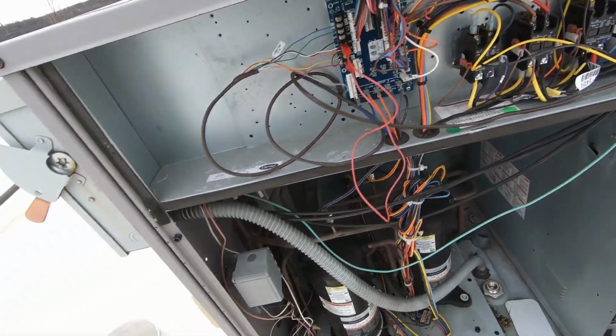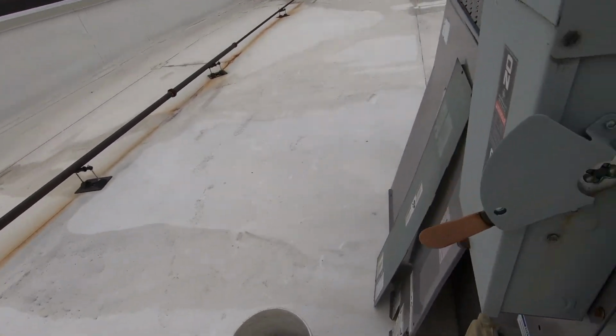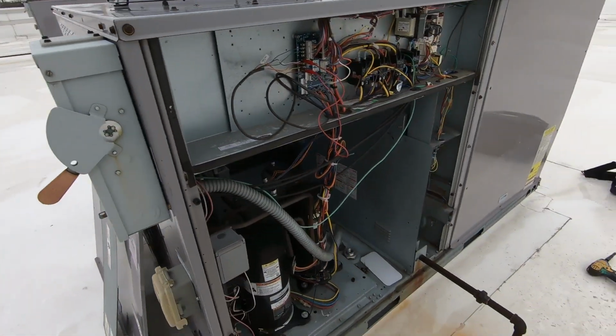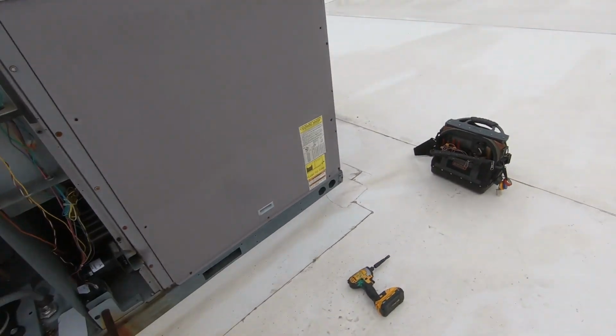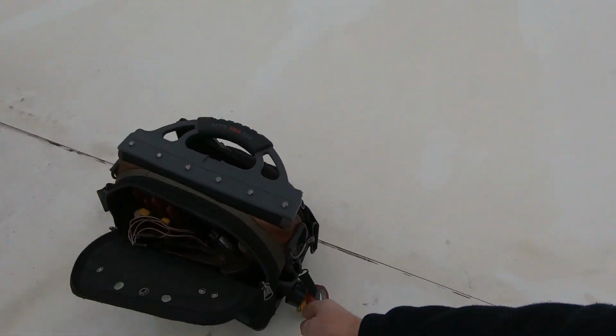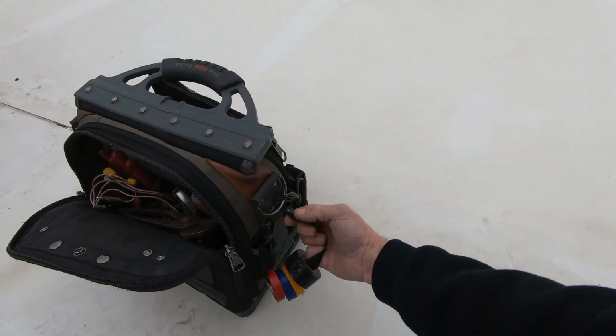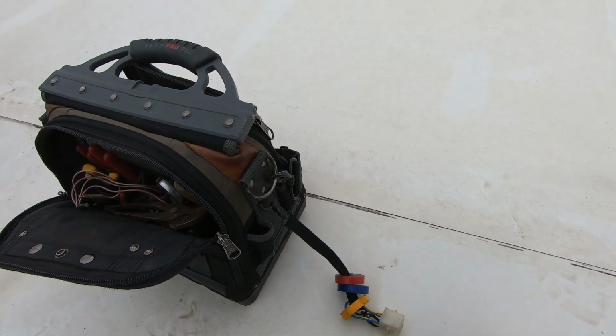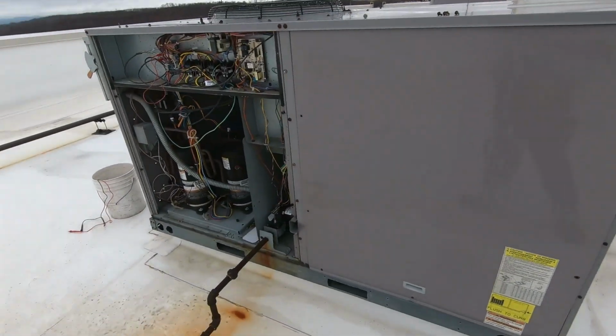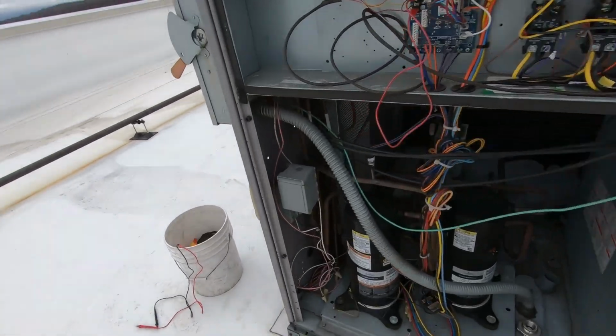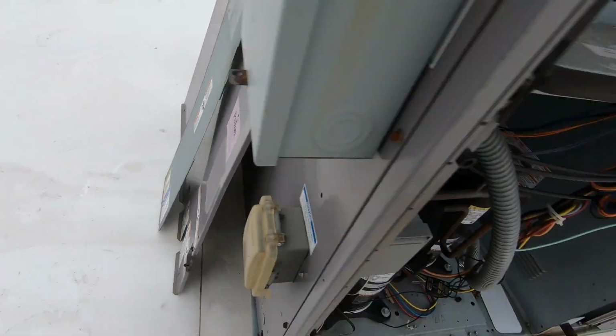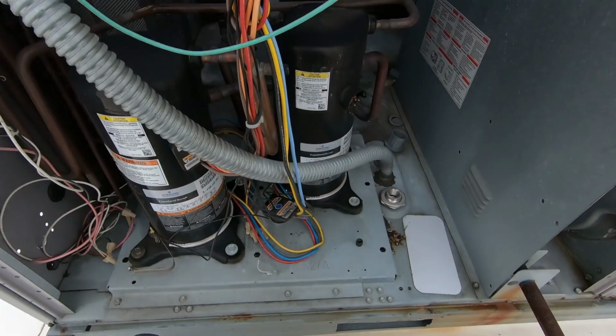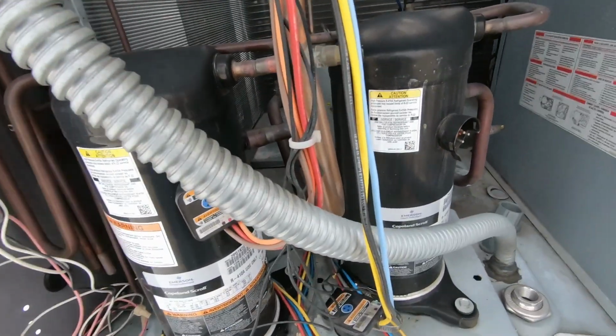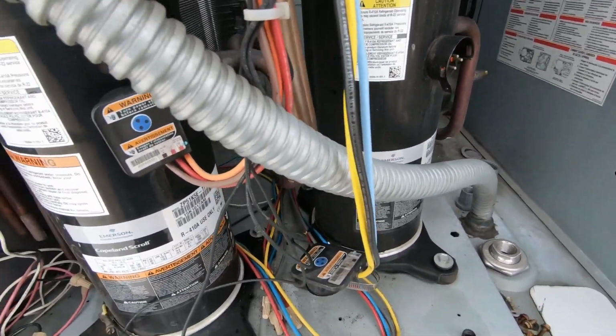Nothing's grounded out. While I got the power off, I'm gonna put a little bit of tape around that plug just to prevent water from getting into it if it hasn't already. That's another thing. If you're ever pulling a plug, wrap some tape around it, guys. But we're talking about the same guy who probably bypassed the high limit and almost burnt that unit in this building to the ground.